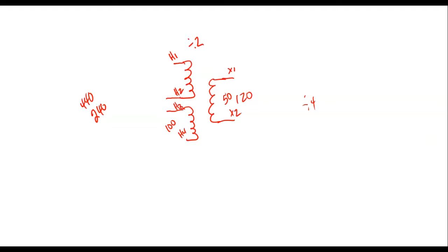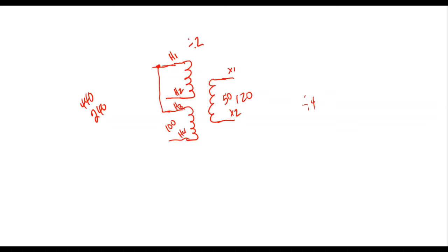So what I'd have to do is come up here, and you got to do this right. I'd have to have H1, and connect it to H2. If I connected H1 to H4, then the transformers would be what we call bucking. It wouldn't hurt the transformers, but you'd get 0 volts because the two primaries would cancel each other out.